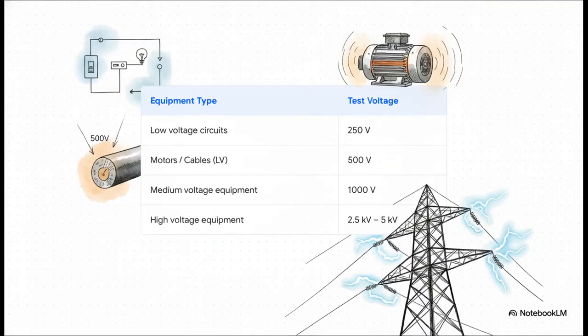Now, you can't just use the same test voltage for everything. It's not one size fits all. The voltage you use has to be scaled to the equipment's rating. So a small circuit might get tested with 250 volts, but some serious high voltage equipment, that might need up to 5,000 volts to really put its insulation to the test.